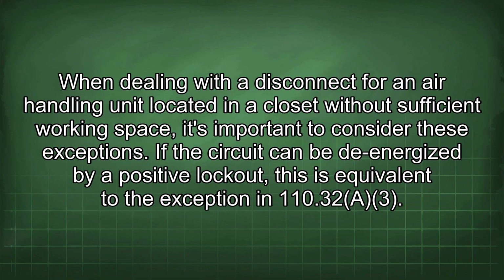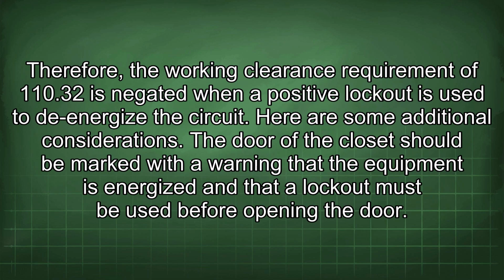When dealing with a disconnect for an air handling unit located in a closet without sufficient working space, it's important to consider these exceptions. If the circuit can be de-energized by a positive lockout, this is equivalent to the exception in 110.32a3. Therefore, the working clearance requirement of 110.32 is negated when a positive lockout is used to de-energize the circuit.